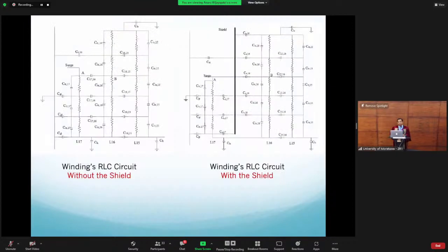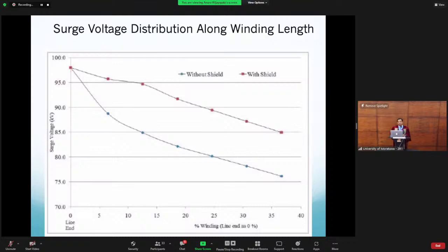We simulated this and found the bottom graph shows the surge voltage distribution along the transformer high voltage winding without the shield, where in 5% of the winding about 15-20% of the voltage is distributed. Whereas with the shield inserted, the upper graph shows a very uniform distribution. Even at 10%, only a small surge voltage appears, which prevents turn-to-turn insulation failure when a surge enters the winding.